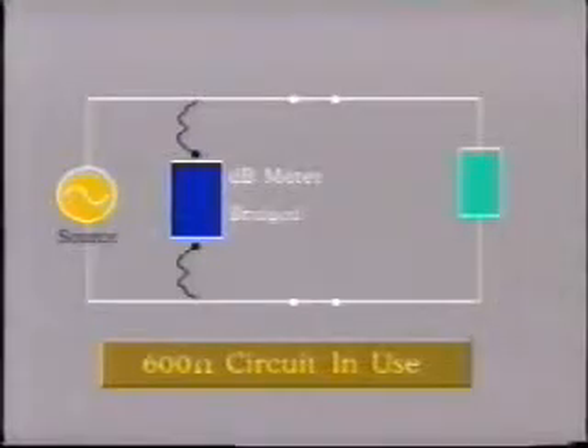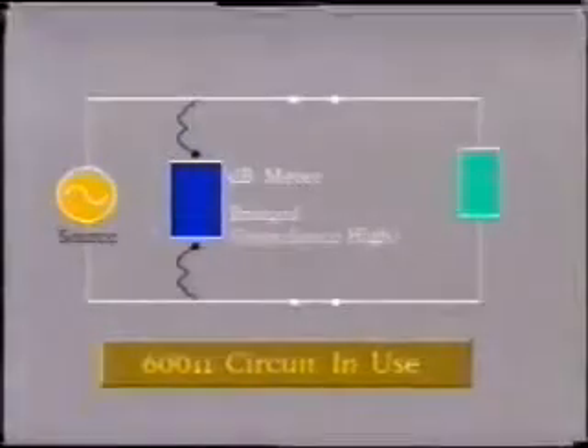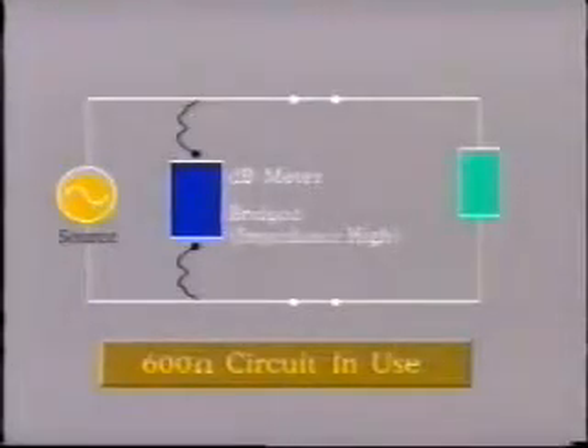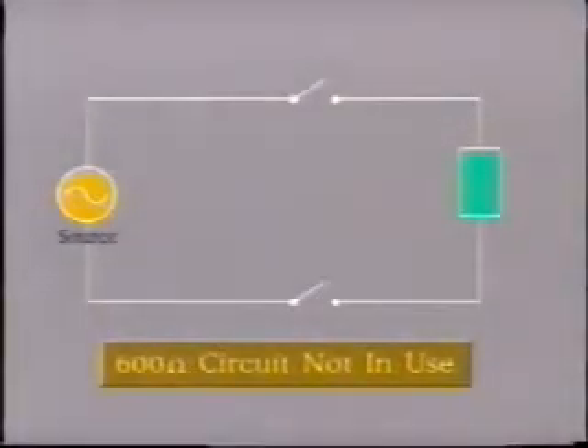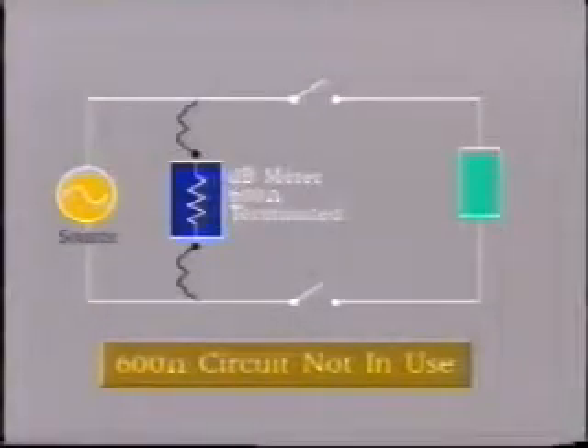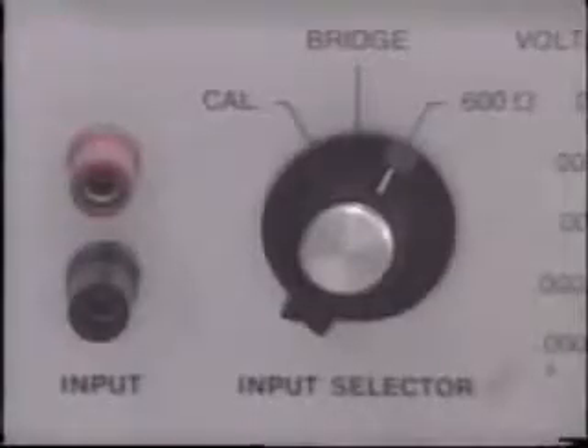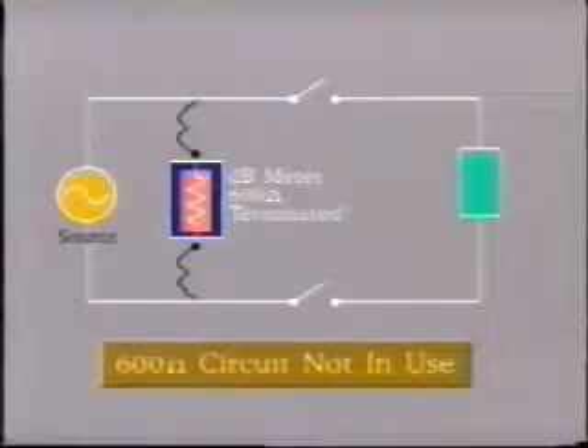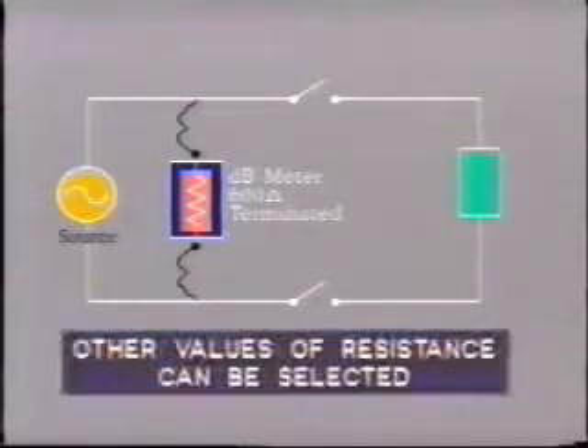In the bridged position, the impedance of the meter is high, therefore having negligible effect on the circuit. However, in some cases, you may wish to measure the signal strength directly from a transmitter or signal generator with the outgoing circuit disconnected. For this purpose, the selector should be switched to the terminated position. This will now switch a 600 ohm resistor across the output to simulate the circuit impedance. Other values of resistance can be selected, say 50 or 75 ohm, depending upon the reference values required.